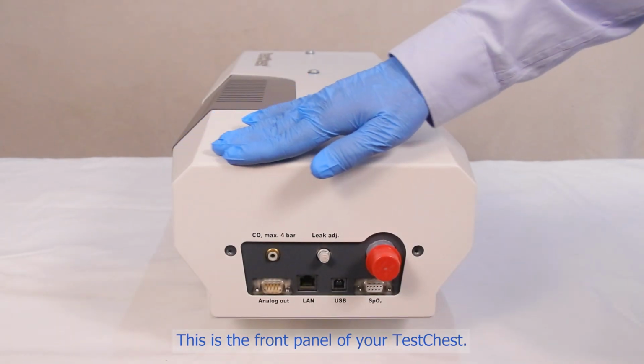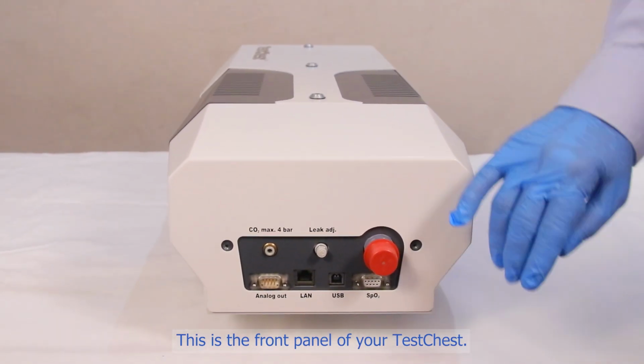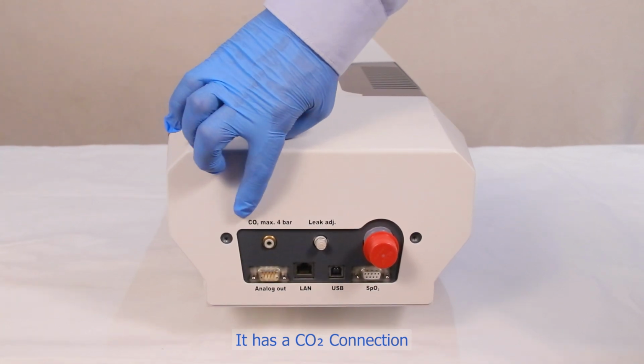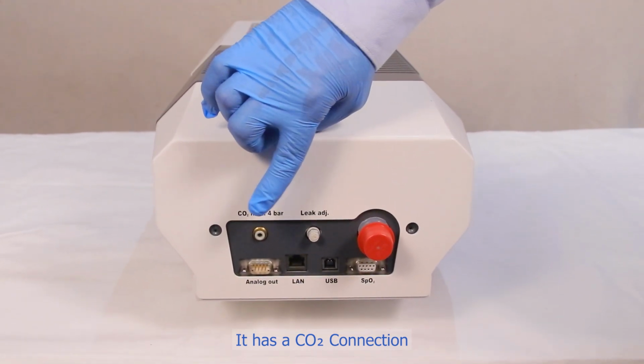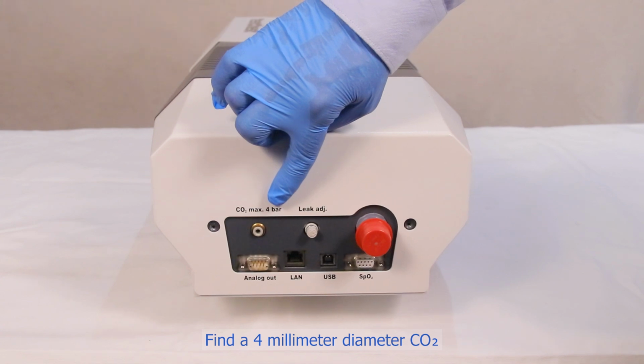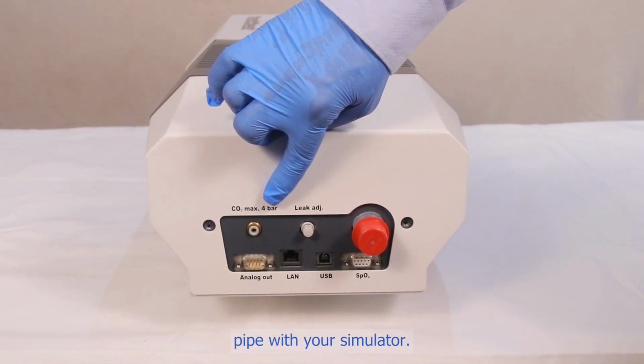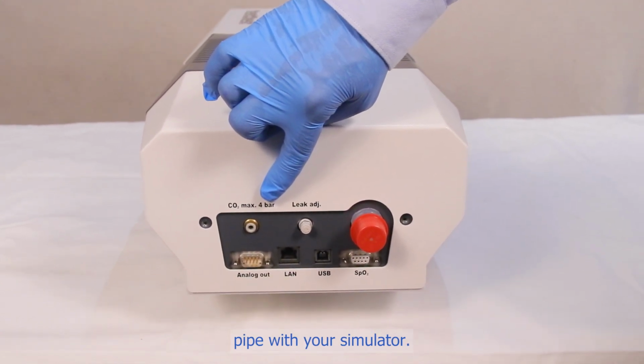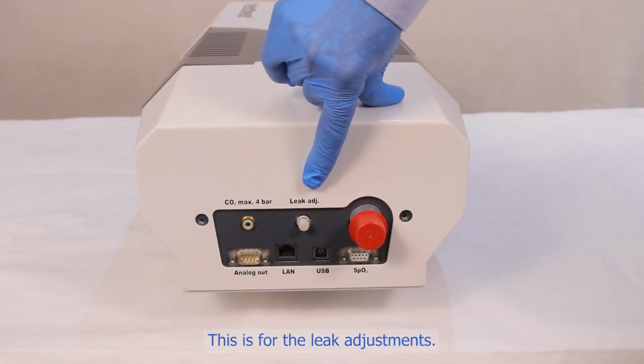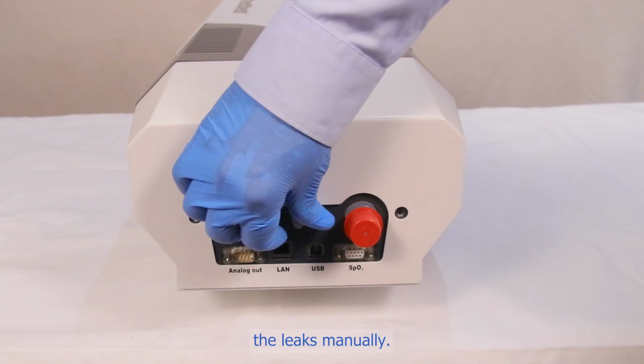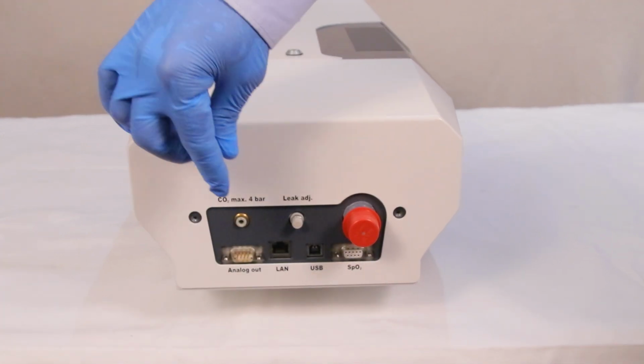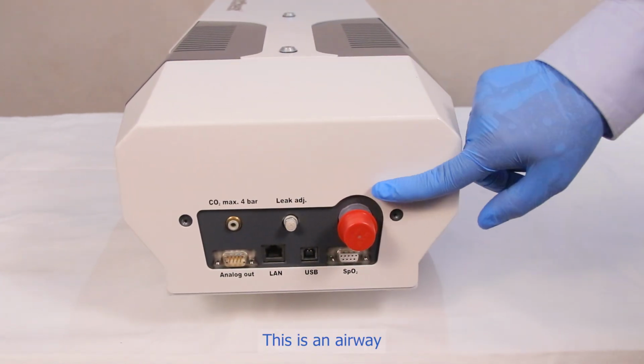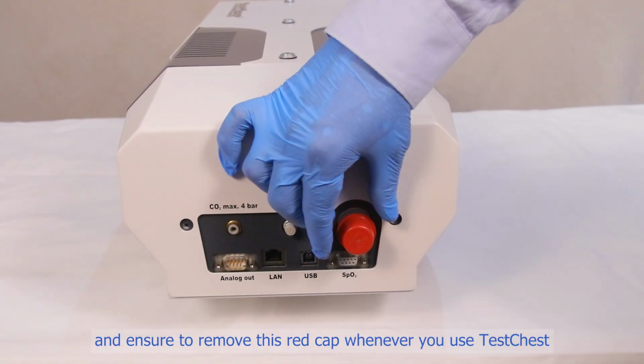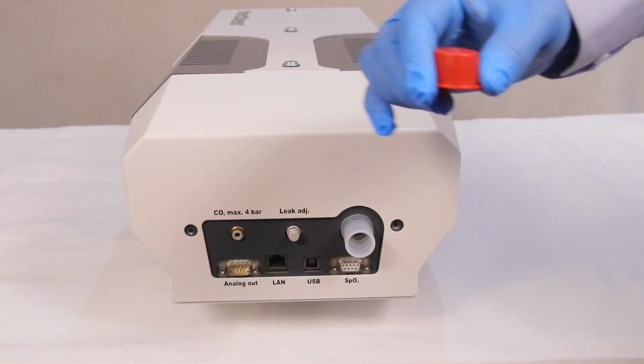This is the front panel of your TestChest. It has a CO2 connection. Find a 4 mm diameter CO2 pipe with your simulator. This is for the leak adjustments. You can open or close to increase or decrease the leaks manually. This is an airway, and ensure to remove this red cap whenever you use TestChest.